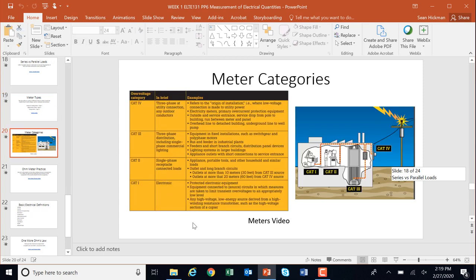Here are our meter categories: CAT 1, CAT 2, CAT 3. CAT 3 is what the DMM and the clamp-on were, and the key thing here is that these are used for three-phase distribution. When you go into a manufacturing facility, you are likely going to see three-phase power — that's what runs factories, manufacturing facilities, and power plants. So you need a CAT 3 meter so that it is rated for the proper voltage at three phase. The Simpson was a CAT 2 and that's used for single phase. The Simpsons might be better suited for a laboratory environment as compared to an industrial environment, because in industrial you're going to need to have a CAT 3 meter.